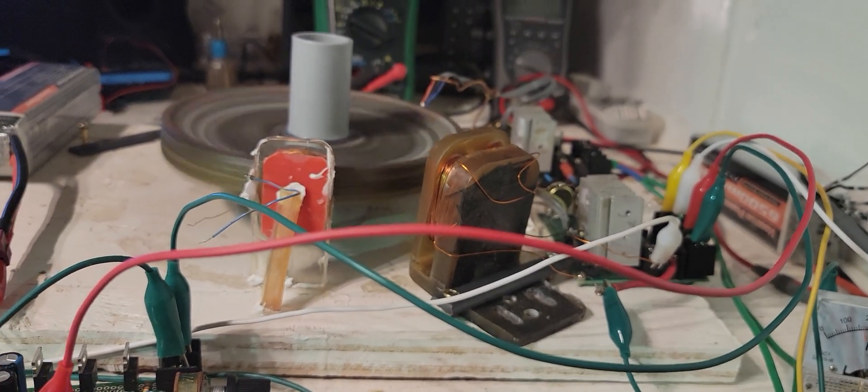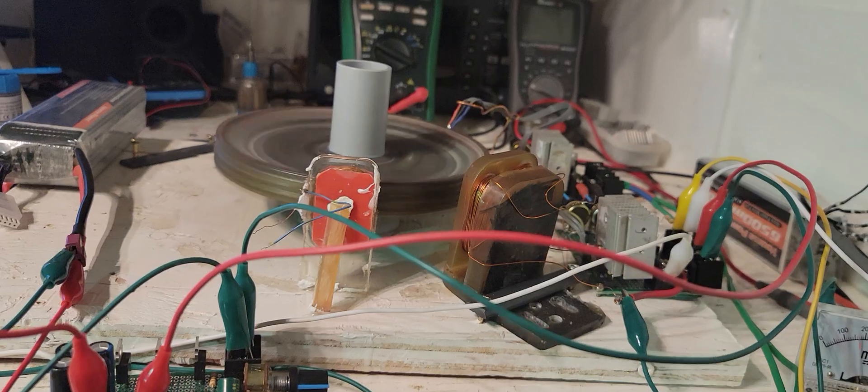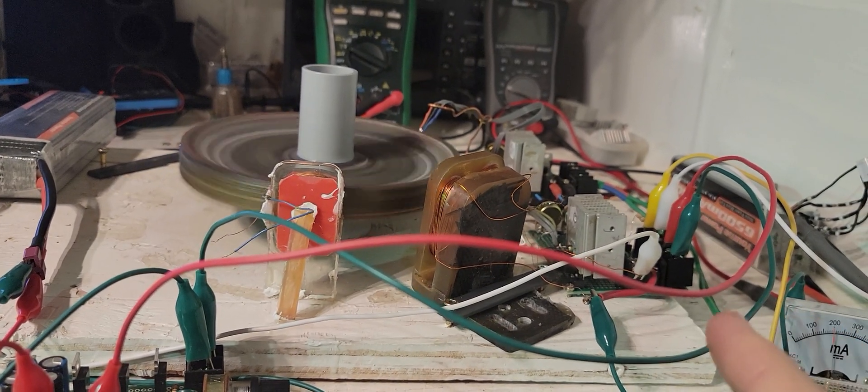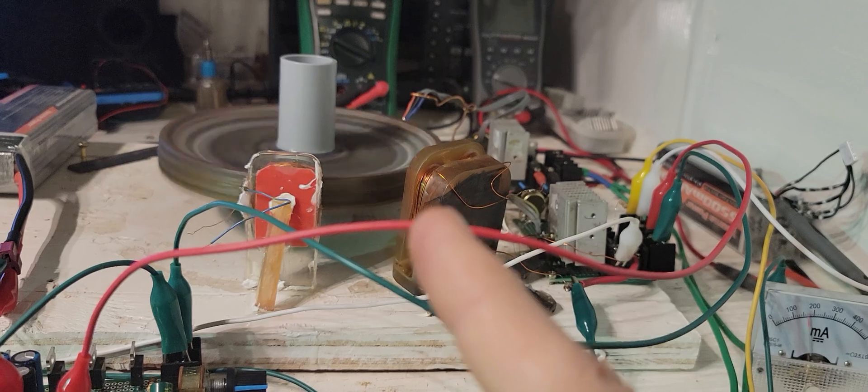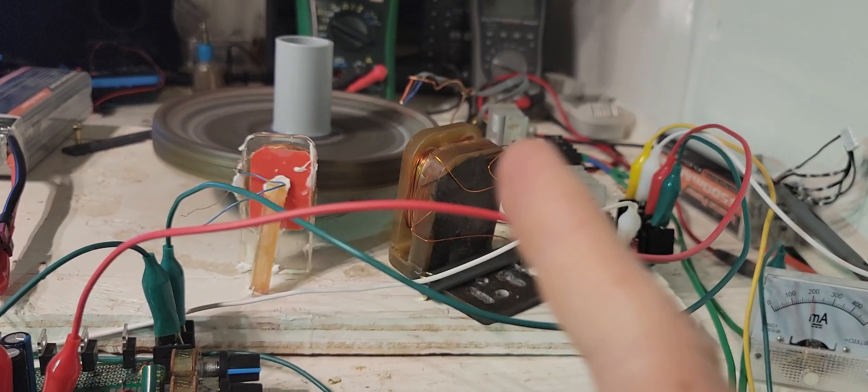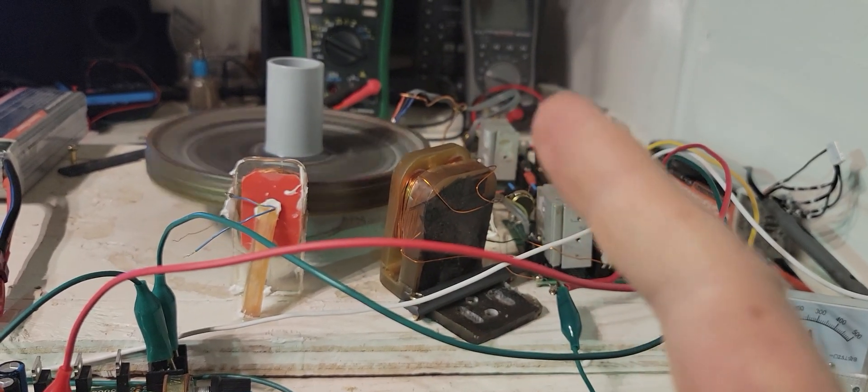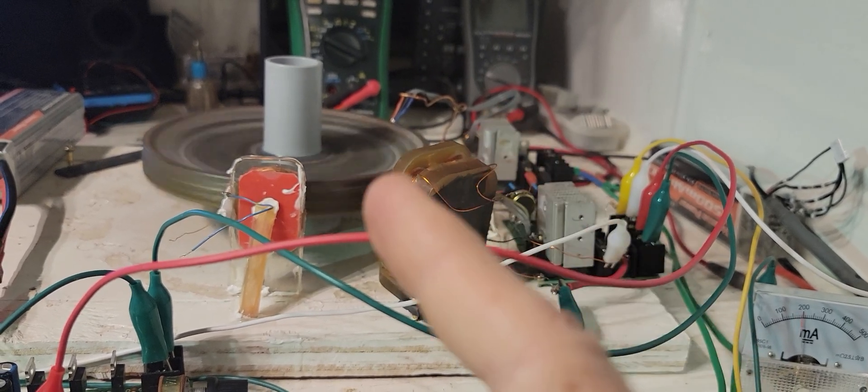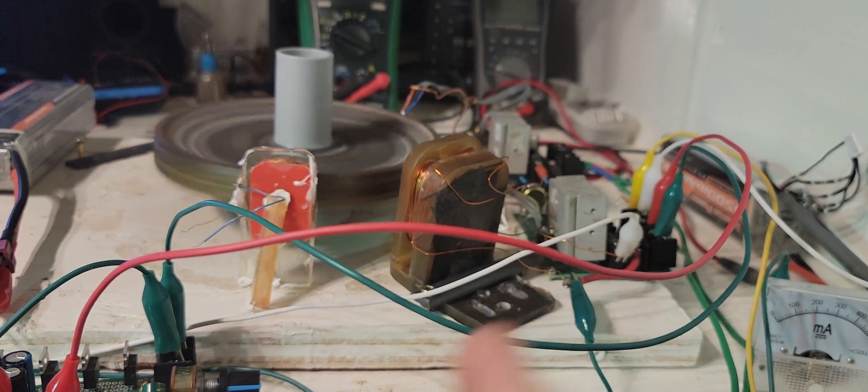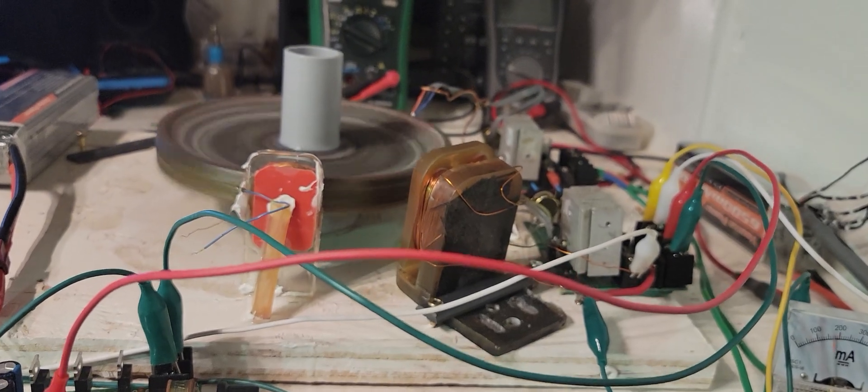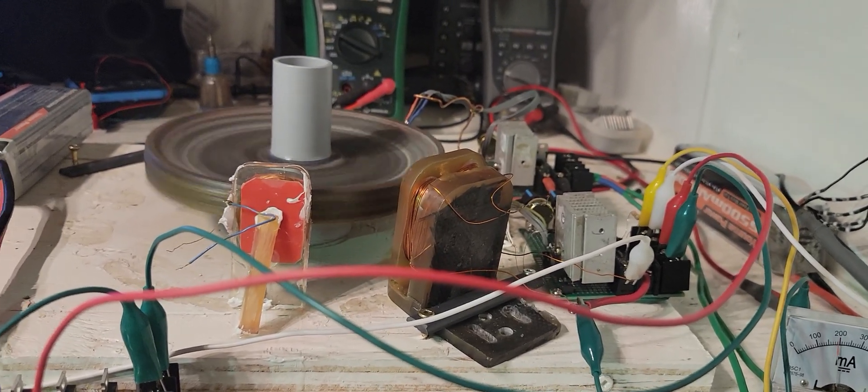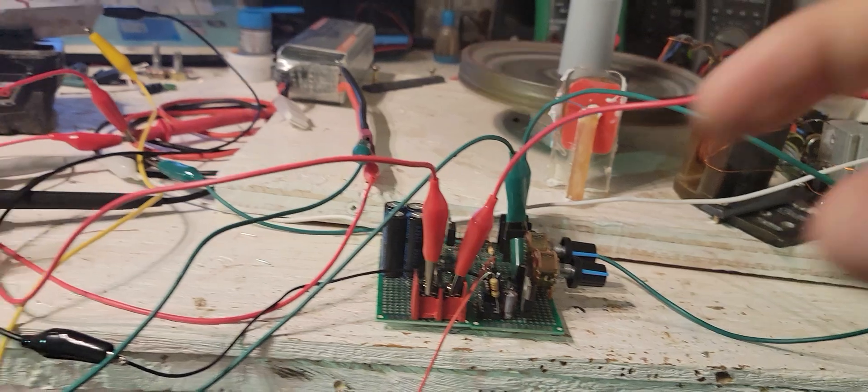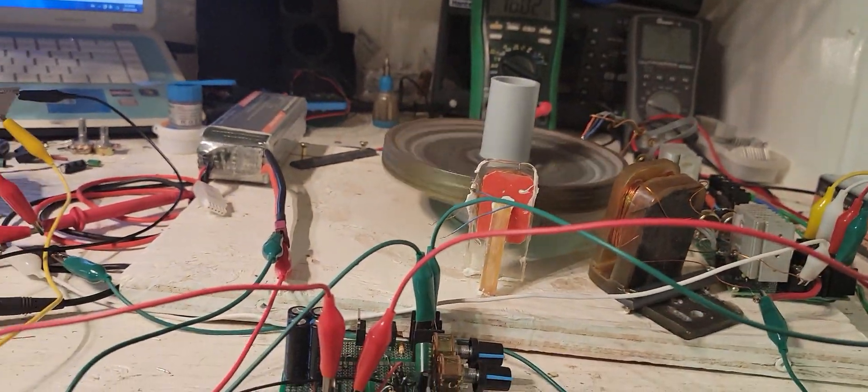that happens with those SCR circuits is if you're running your motor right at the verge of where you only have it at the minimum requirement for it to trigger. If your input voltage drops enough, then your current that's triggering the SCR, your voltage and current is going to be too low and it won't trigger it. Whereas this one is always going to trigger, no matter how low your voltage gets.